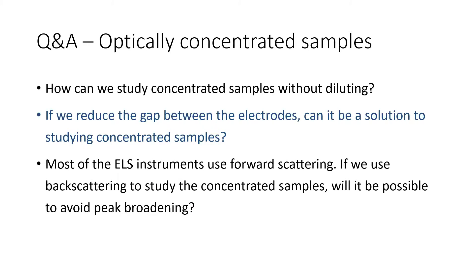Question: most of the ELS instruments use forward scattering. If we use backscattering to study concentrated samples, will it be possible to avoid peak broadening? Backscattering is used for particle sizing by dynamic light scattering. In backscattering mode, the instrument looks at light scattered from randomly moving particles close to the cuvette wall on the same face as the incident light. This means there is minimal chance of multiple scattering, the cause of peak broadening.